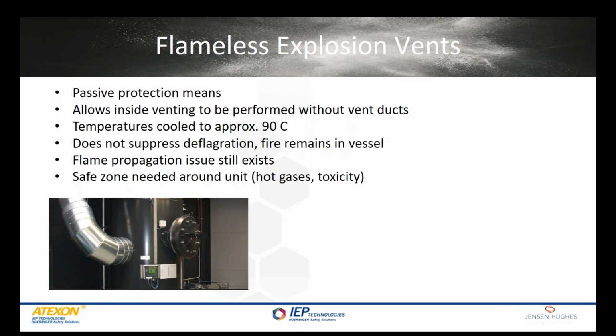Now, we do have to keep in mind that 160 to 200 degrees F will scald someone. So there is still a safe area requirement around the perimeter of these flameless explosion vents. Typically 2 to 3 meters, depends on the type of vent it is, depends on the application, even depends on the distance. But oftentimes flameless vents are a good alternative to regular vents with ducting.